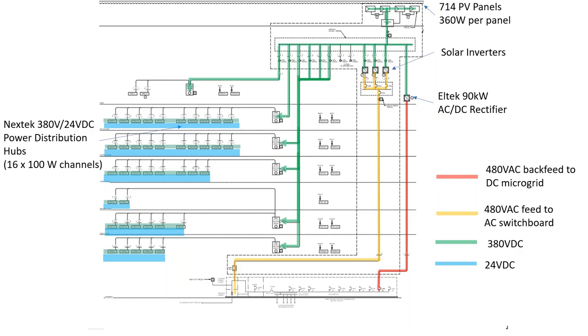For the DC microgrid to function as described above, it will depend on the 380 volt DC voltage levels produced by the PV system and a voltage set point assigned to the inverter. The voltage set point assigned to the inverter will allow the inverter to only invert the excess power produced by the PV system. This set point is typically between 382 volts DC and 383 volts DC.